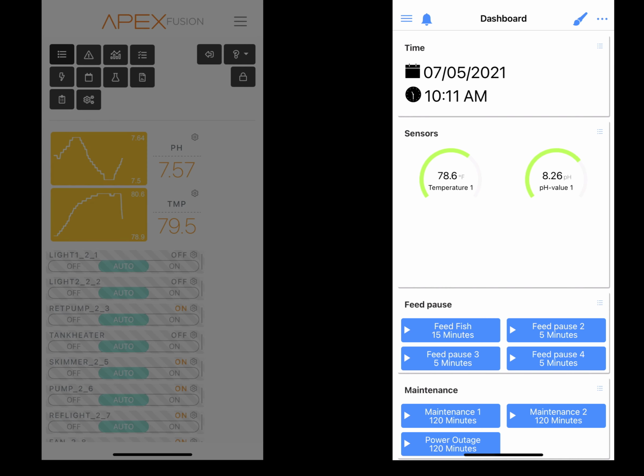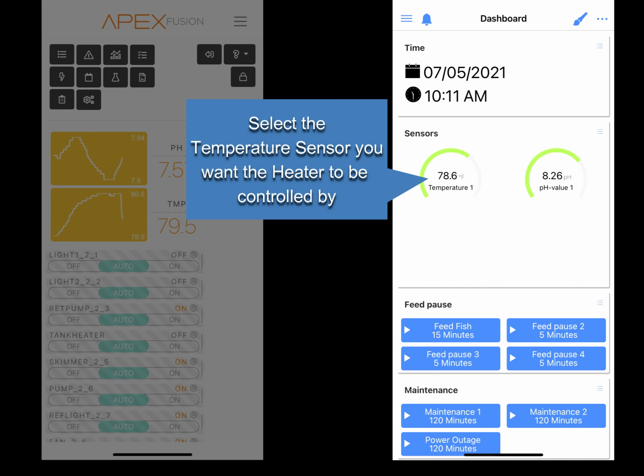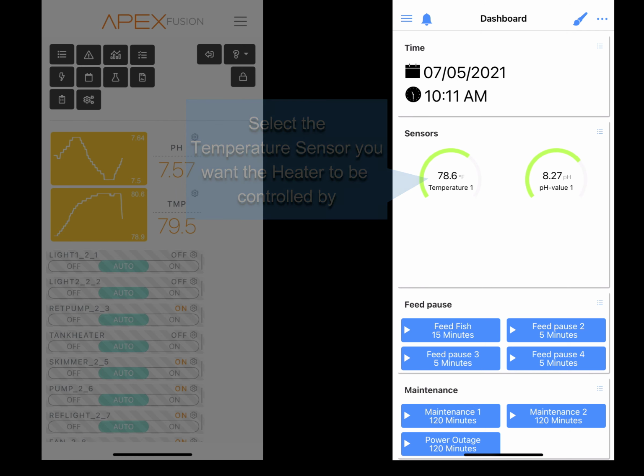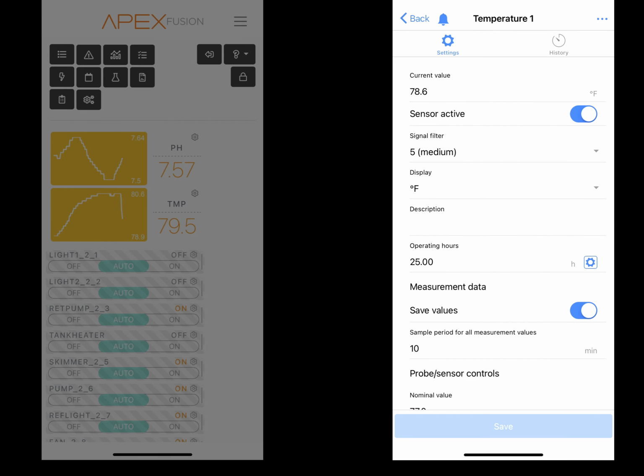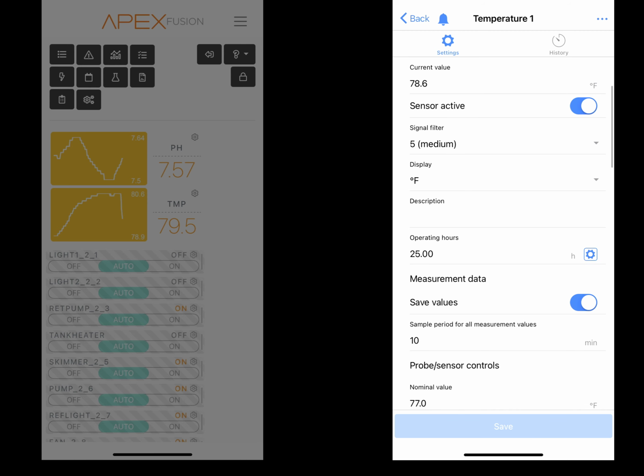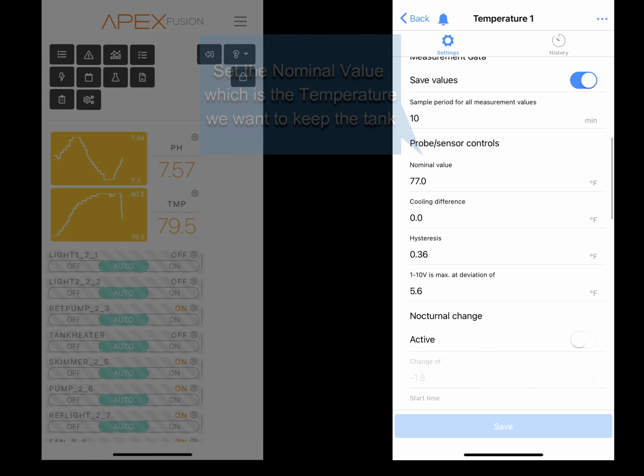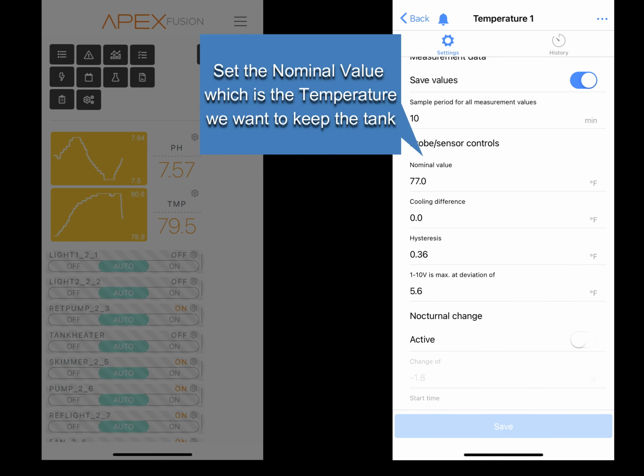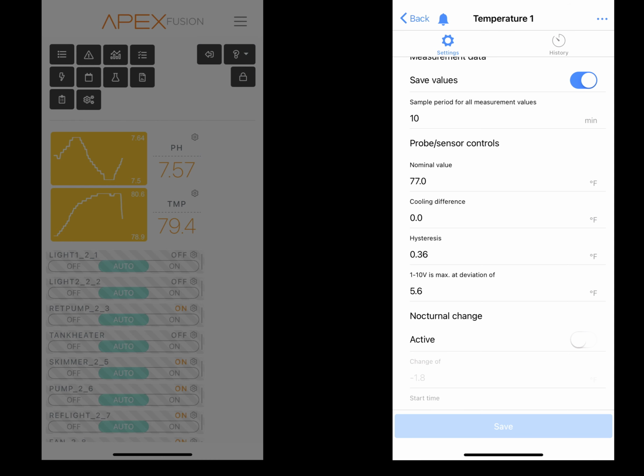How do you set the temperature to turn on and off the heater and apply it to an outlet for the GHL controller? On the GHL controller, select the temperature sensor you wish the heater to be controlled by. This will direct you to the temperature sensor page. We need to first set a nominal value. Scroll down to the probe sensor controls. The nominal value is the temperature we wish to keep the tank at. I'm setting the nominal value to 77 degrees.